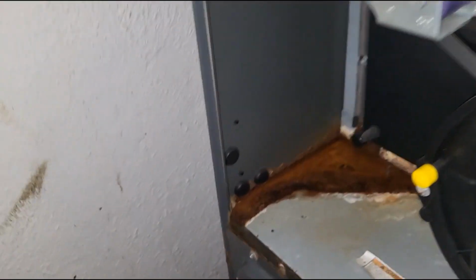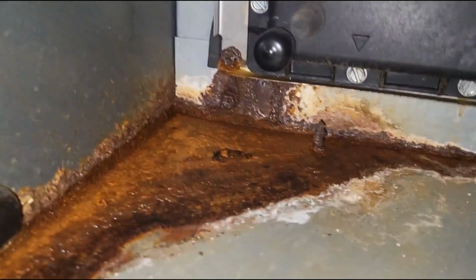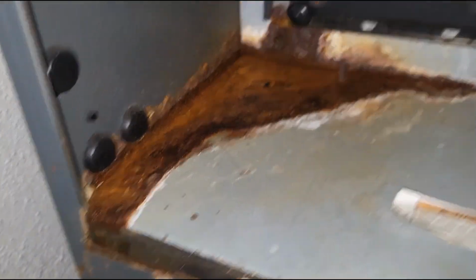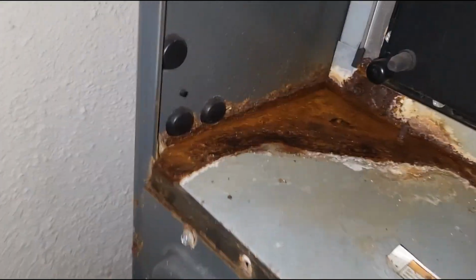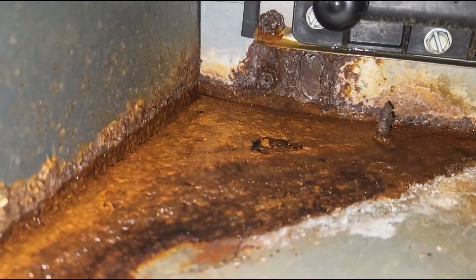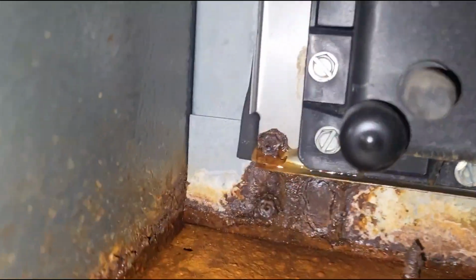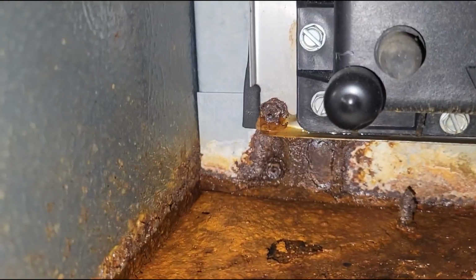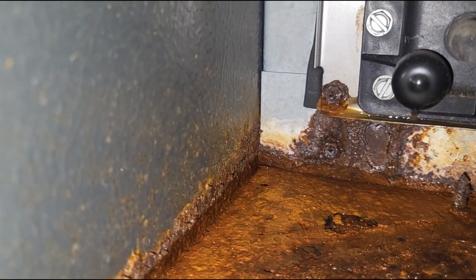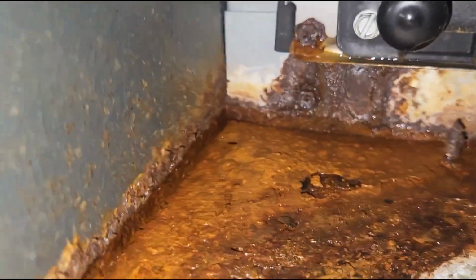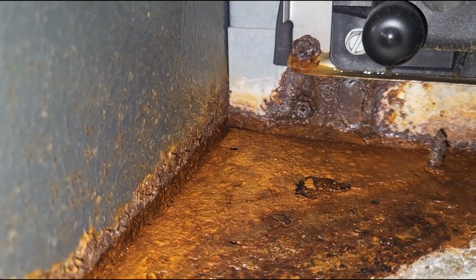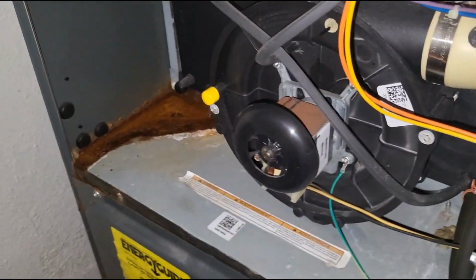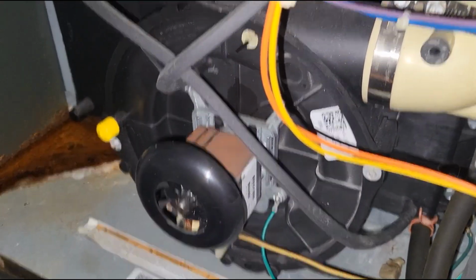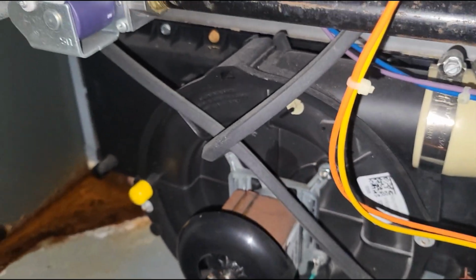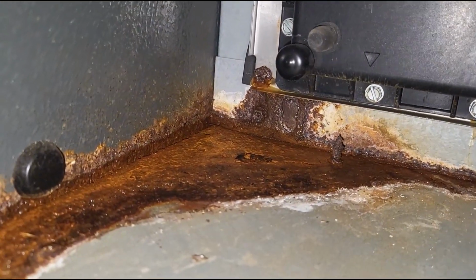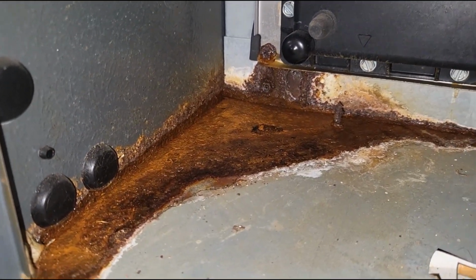And guys, look at this. This can't be good. And this is dry, but it looks like at some point in the past... I don't know if that's coming from the actual collector box or if it's coming from the screw in the back of the furnace. That's not good. But the only way to diagnose that is we'll have to pull the inducer, and we can pour water in the collector box and see if it leaks from this end. But like I said, guys, this is all dried up, which is crazy.